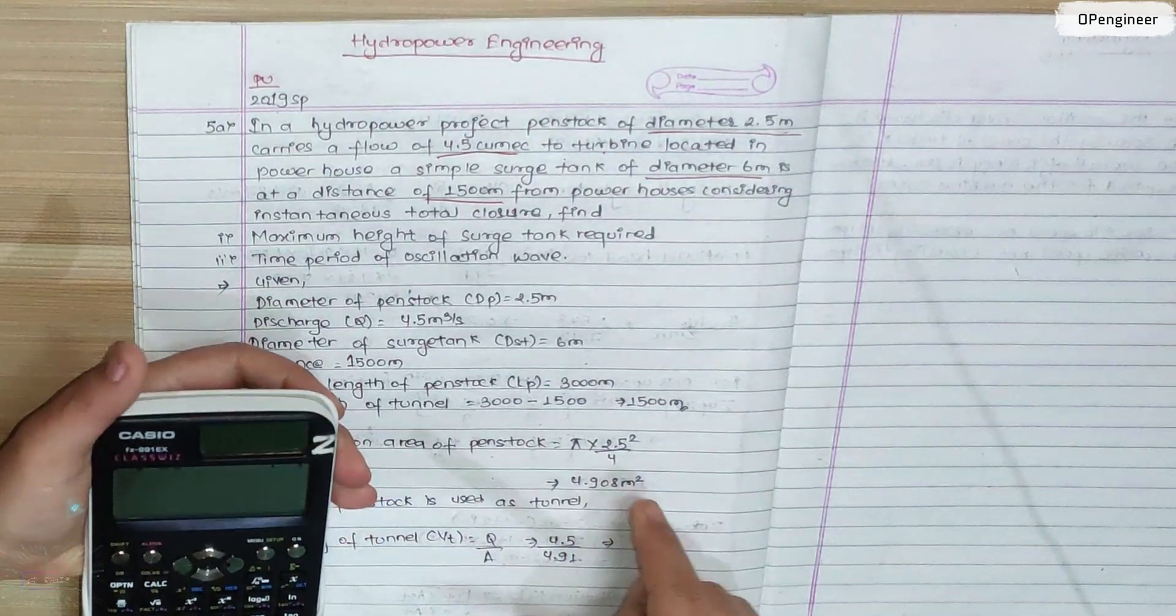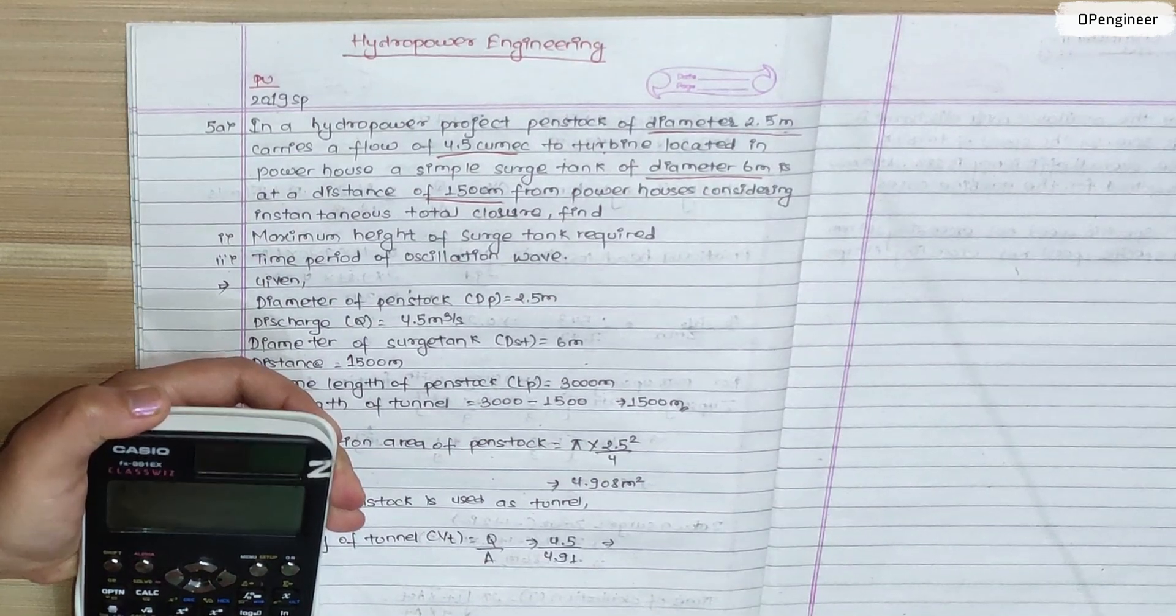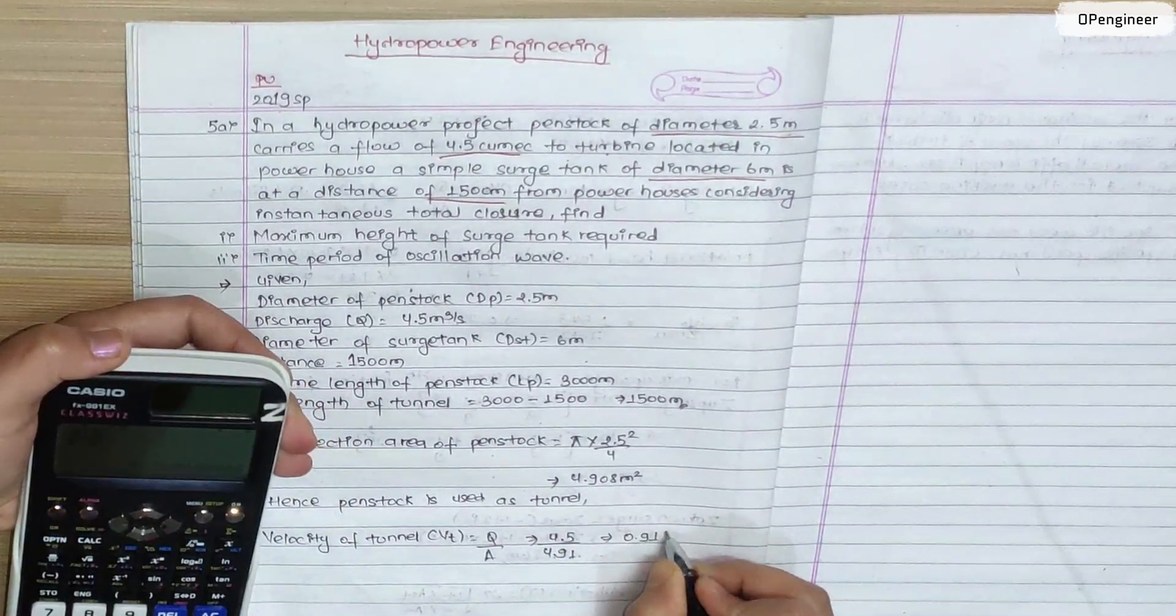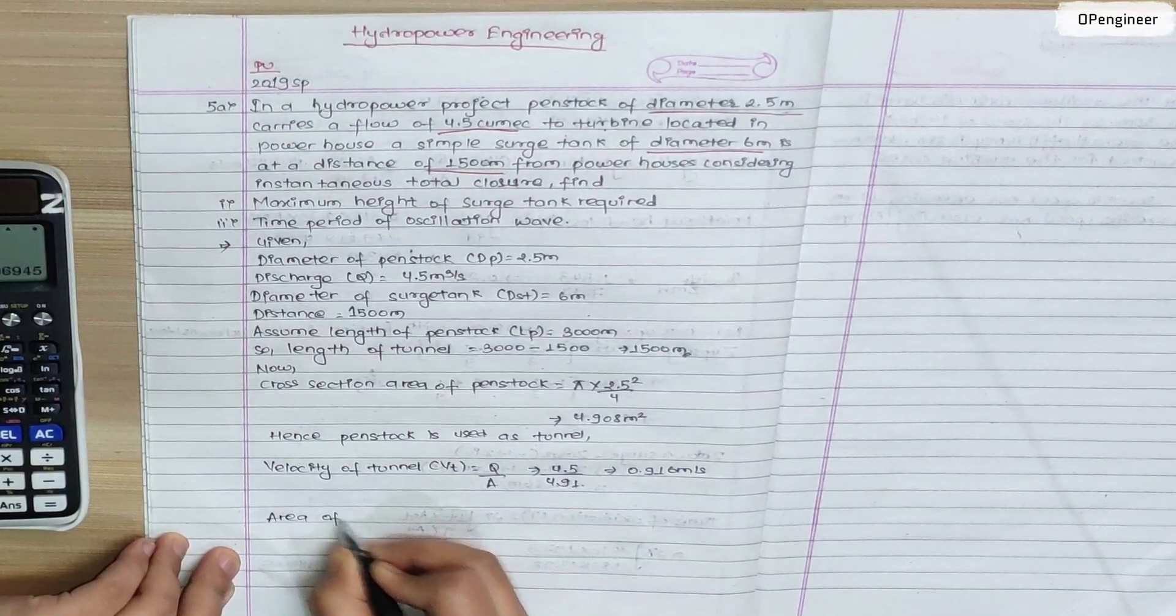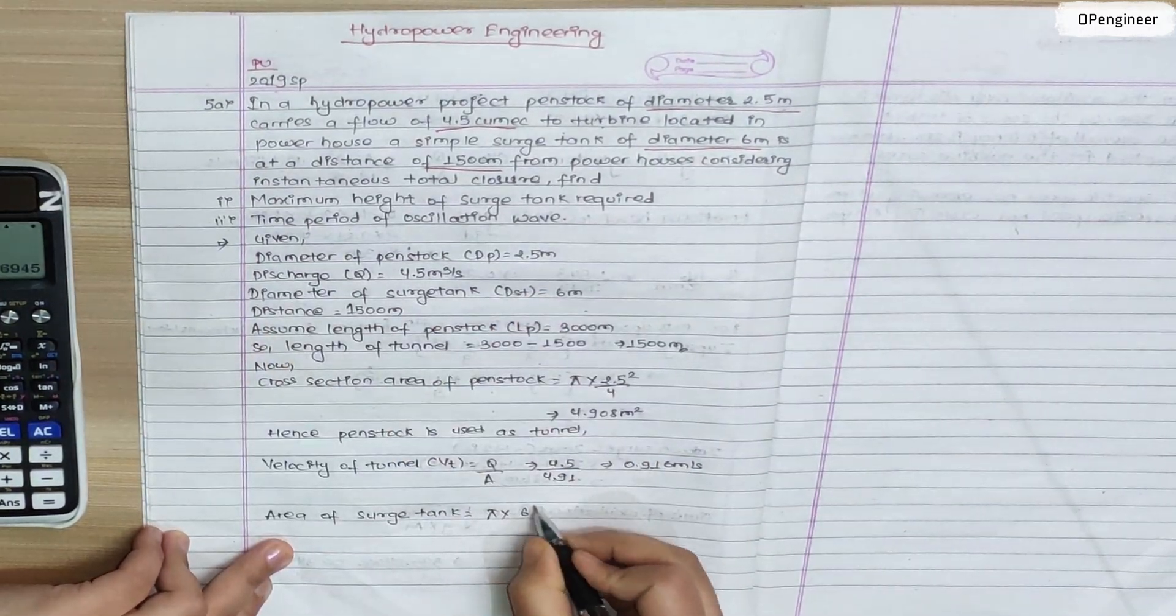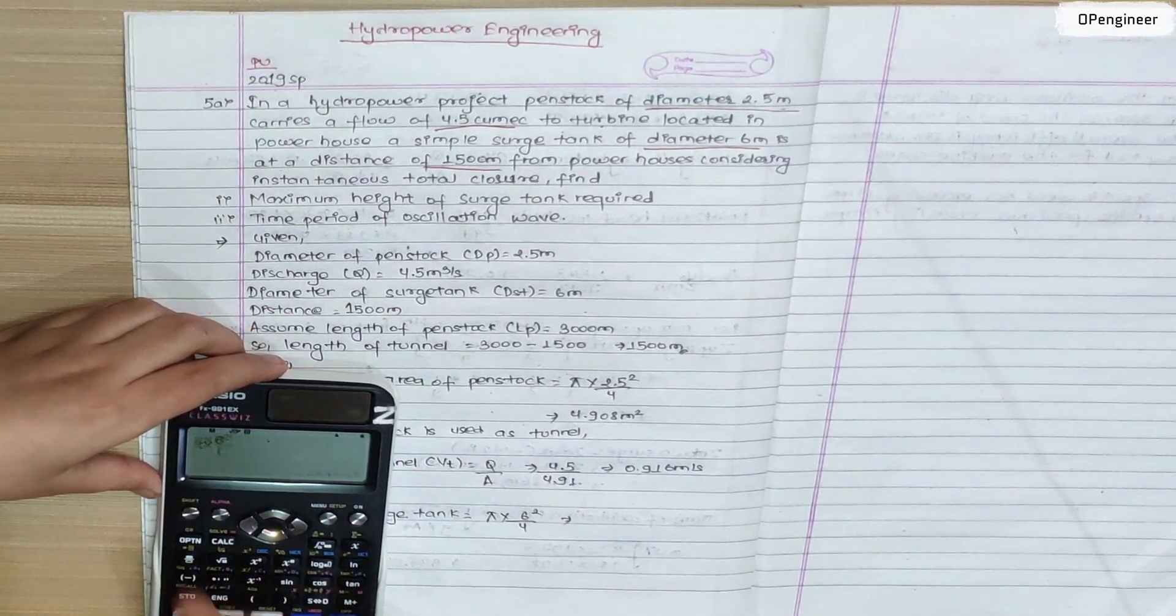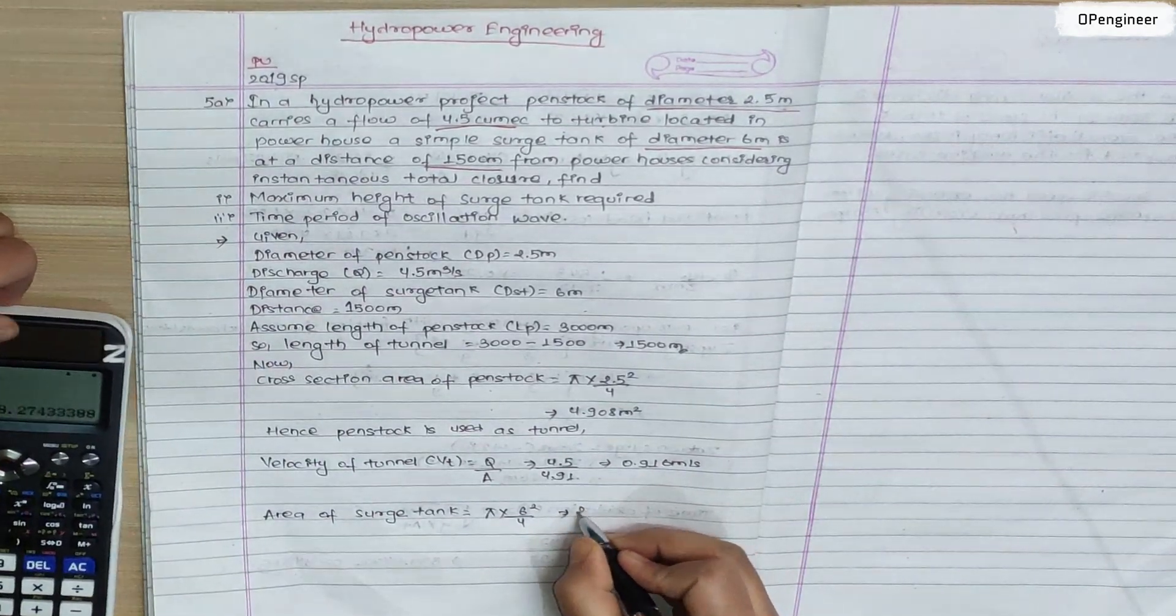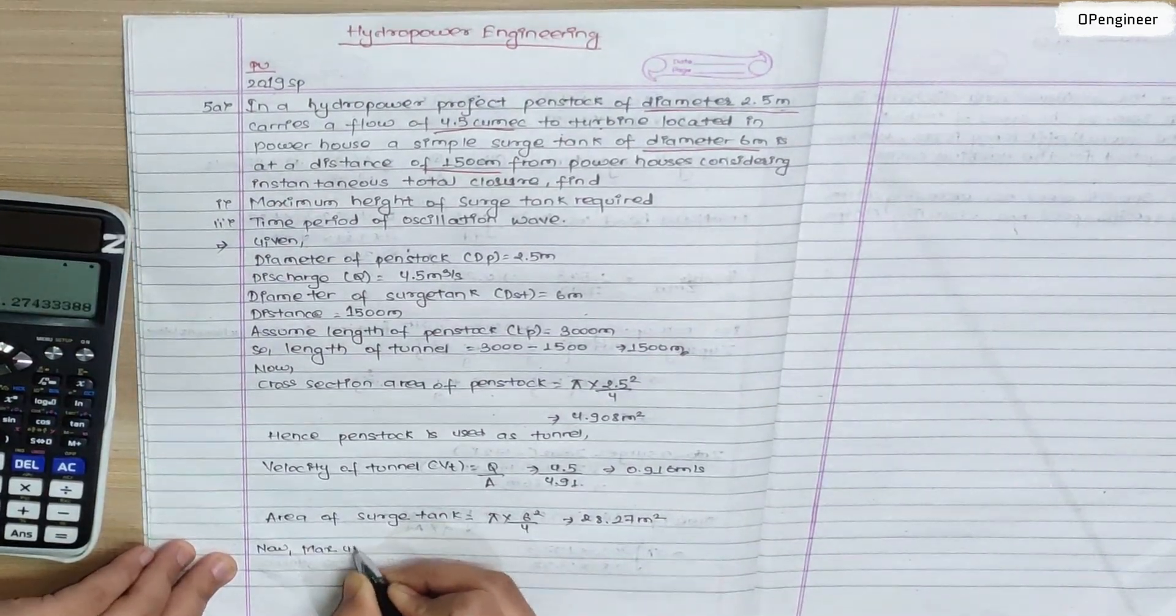So 4.5 by 4.91, you calculate that is 0.916 meter per second. Now, area of surge tank: pi into diameter of surge tank 6 meters squared by 4. So pi into 6 squared by 4, you calculate that area of surge tank 28.27 meter square.